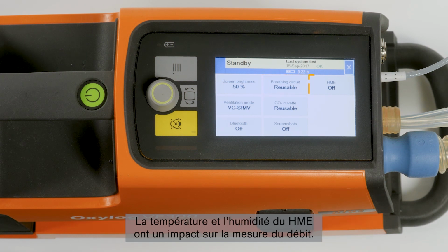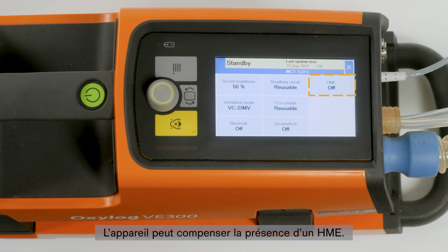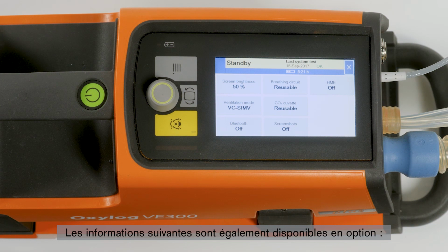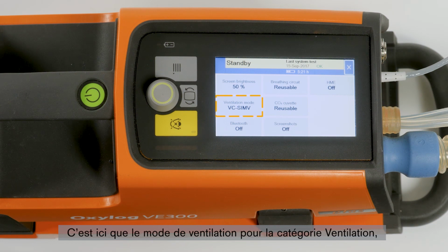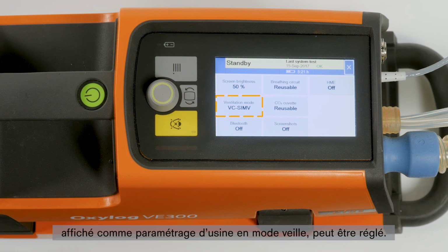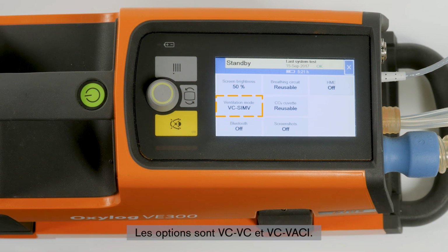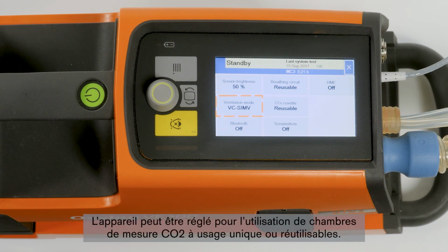The temperature and moisture of the HME have an effect on the flow measurement. The device can compensate for the presence of an HME. The following optional information is also available. The ventilation mode for the ventilation category Ventilation, displayed in standby mode as presetting, can be set here. The options are VC-CMV and VC-SIMV. The device can be set for the use of disposable or reusable CO2 cuvettes.